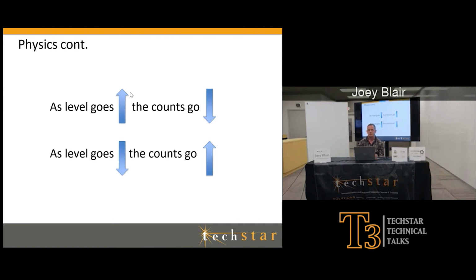Well, actually, let me back up. I've got two choices here. Let's say I don't have the ability to really fill it and watch it as it fills. Okay, that's out. It's just not going to work. I can get a good zero. I know my zero is good, but I can't do that. I look at the way my detector is installed. I look at the things around me, and I know that if that vessel is completely full of process, I will most likely read zero, or I'm not going to have any radiation coming across that vessel. I can close my shutters on my source over here, and it's going to read a very low amount of radiation. It'll probably read somewhere around 100 counts, 150 counts.